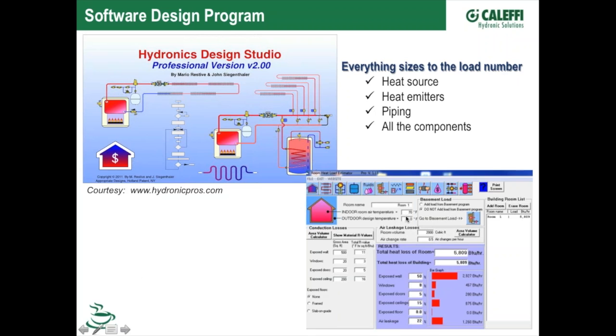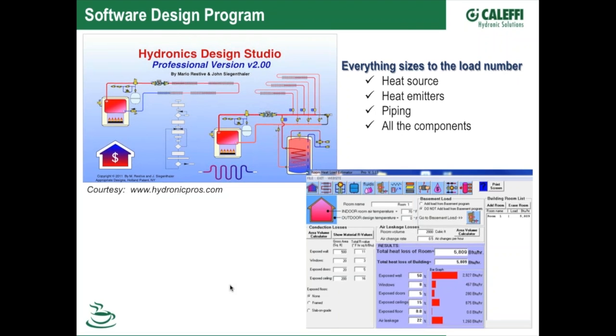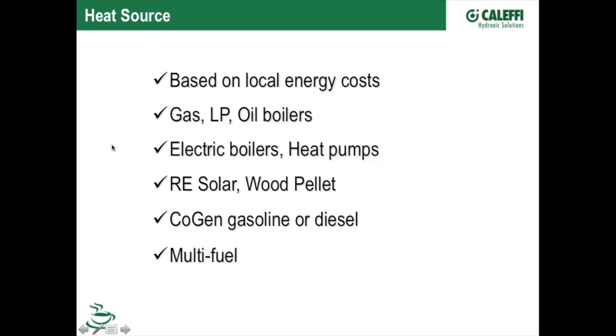This allows you to play with different design conditions, outdoor conditions, indoor conditions. Typically, you'll put in the design for your area. There's a lot of weather information available online. I think Jody talked about some of that in the last presentation. We can go to NOAA websites and get hours of occurrence and different weather information and really get a tight number. But don't ignore this important step. I know a lot of guys just say, well, I do that house in that neighborhood all the time, I'm just going to wing it. Things change in buildings over the years that would change that number, sometimes considerably, if upgrades have been made. So make sure you do that first step.